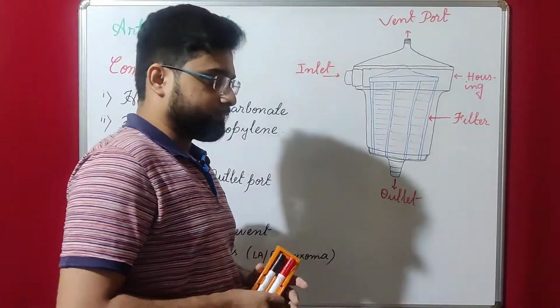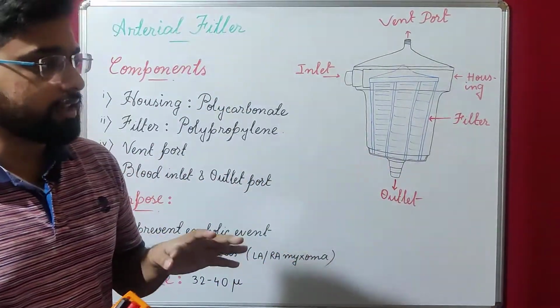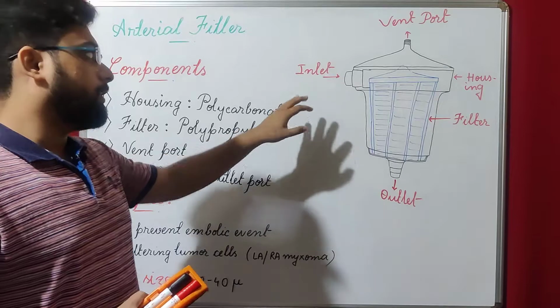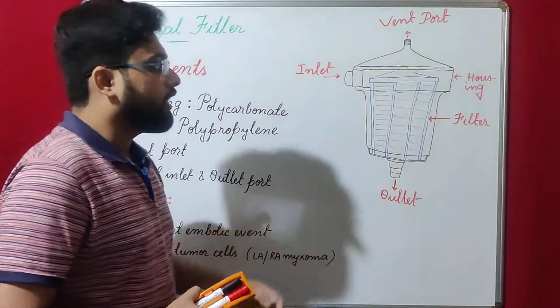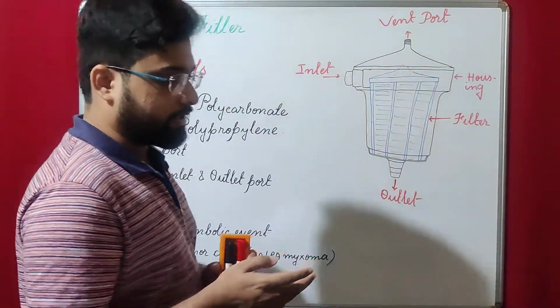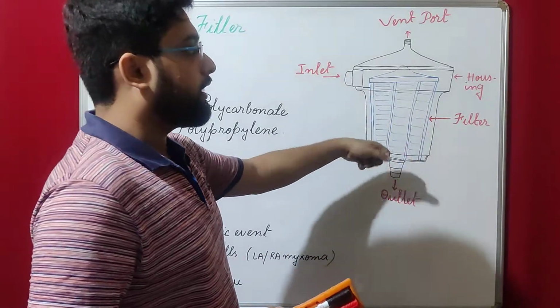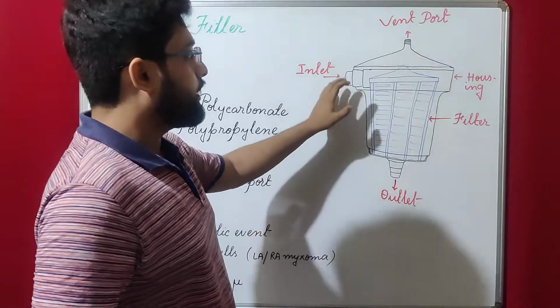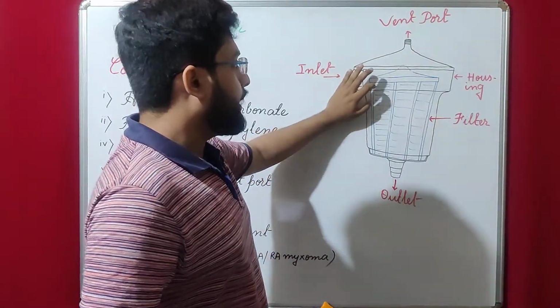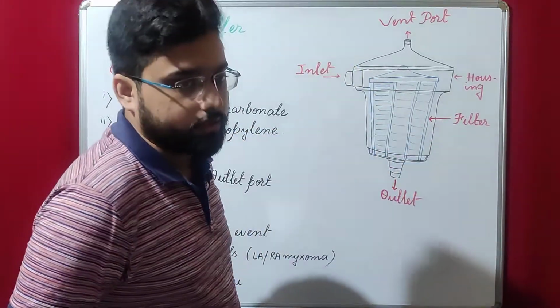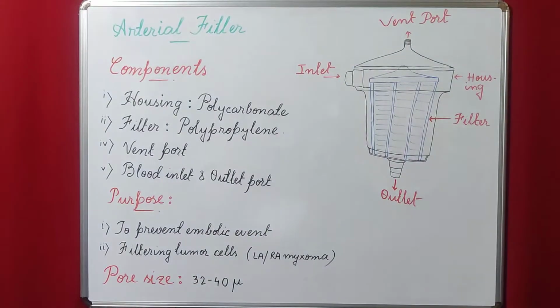We have to give some extra focus on this equipment while de-airing. We have to turn it upside down. We have to hit it. Hit it does not mean increasing the temperature; hit it with a line clamp or some hard equipment, so that there is no air between the surface of the filter and the water. So these are some limitations.